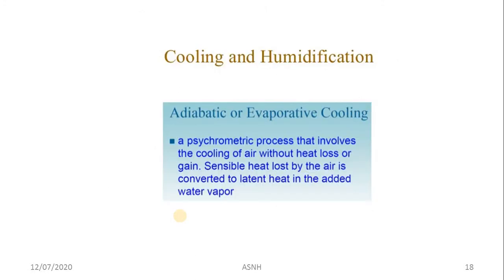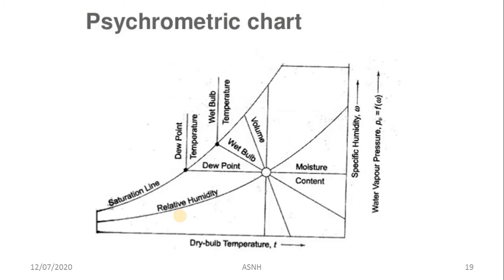Cooling and humidification is the psychrometric process that involves cooling of air without heat loss or gain. Sensible heat lost by the air is converted into latent heat in the added water vapor — this is generally called adiabatic or evaporative cooling. The air cools without any heat loss or heat gain.